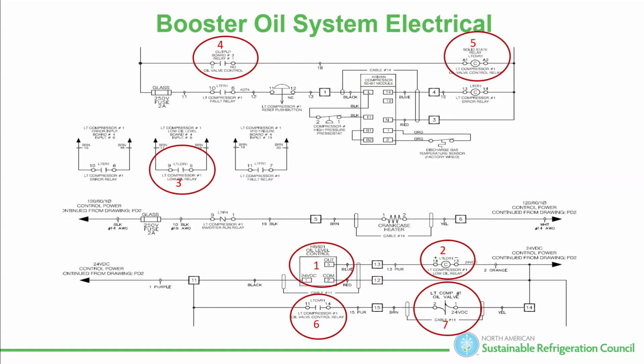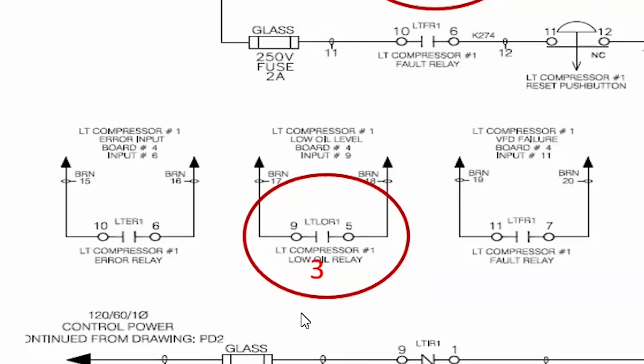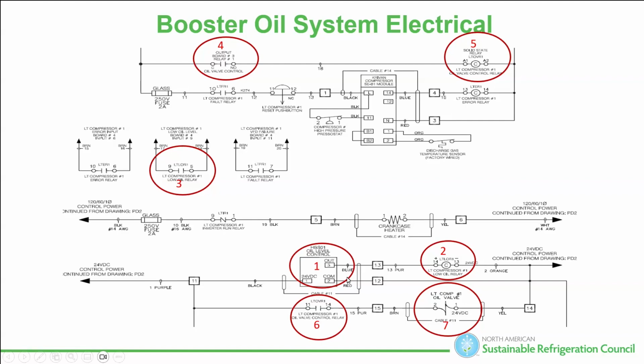I probably have a bad fuse. If it's not, then I'm coming down here to see if I got a digital closure. Is it energized? Because if the controller's not doing what it's doing, maybe I'll check and see. I'd ohm across that to see if I had a closure. If not, I may check right here because the HB sensor simply did not switch from pins 1 to 2, to 1 to 3, and didn't send that 24 volts DC out to energize the coil.